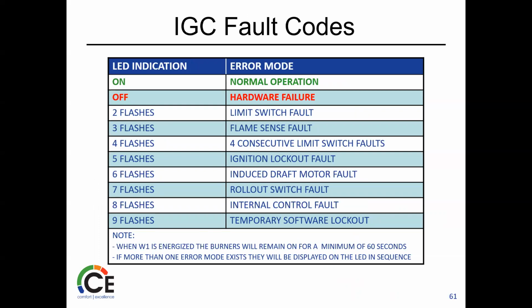Even with the newer boards, the flashes are the same. If you're looking at it and it's on, basic, normal, just sitting there waiting, right? It's in wait mode. If it's off, we've either lost power or we've got a problem with the board, right? So again, we're going to make sure it has power, and then we'll move on and start looking for something else. One of the limit switches open. Remember, on the heat side, not the refrigerant side. You're going to get 2 flashes. If it lost flame, you're going to get 3.